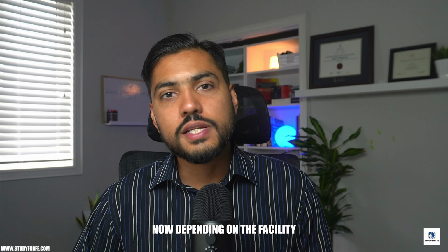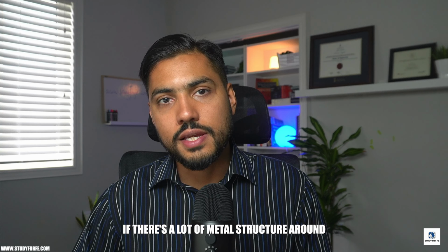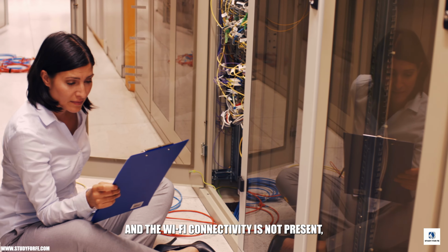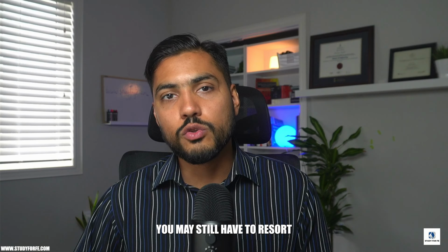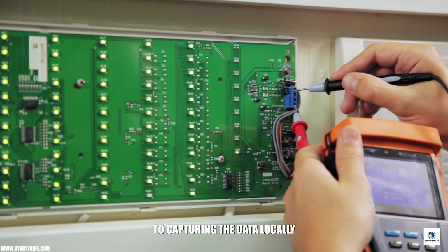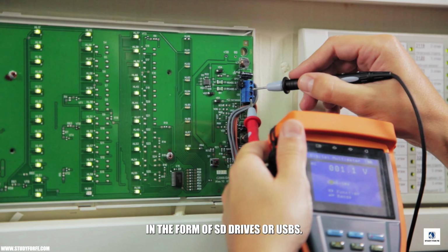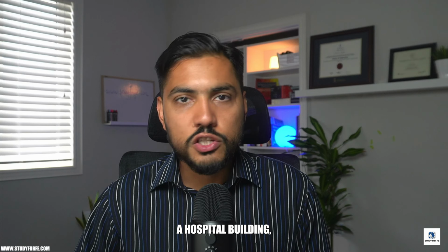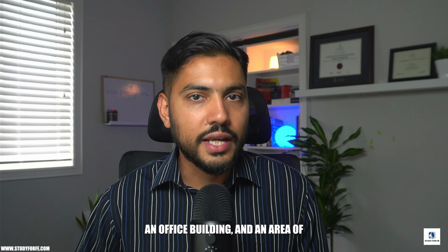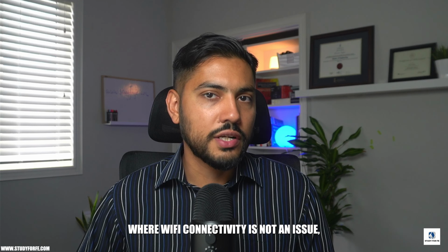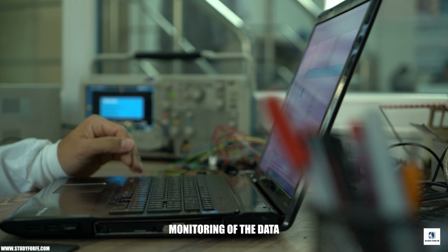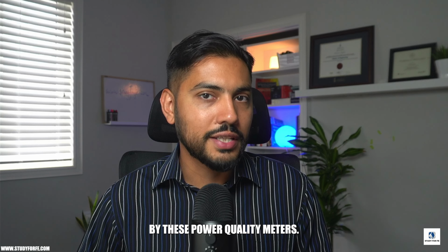Now, depending on the facility where you are conducting the power quality study, if there's a lot of metal structure around and Wi-Fi connectivity is not present, you may still have to resort to capturing the data locally in the form of SD drives or USBs. But if you're in a commercial setting, a hospital building, an office building, an area where Wi-Fi connectivity is not an issue, you can actually do real-time monitoring of the data that is being recorded by these power quality meters.